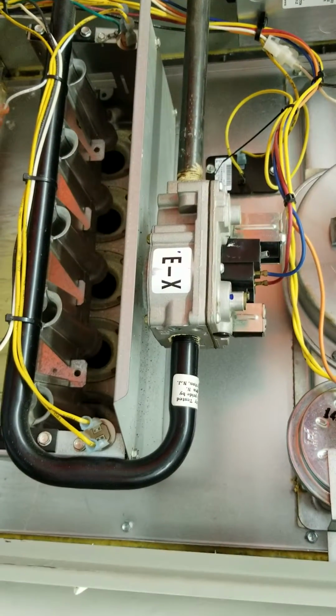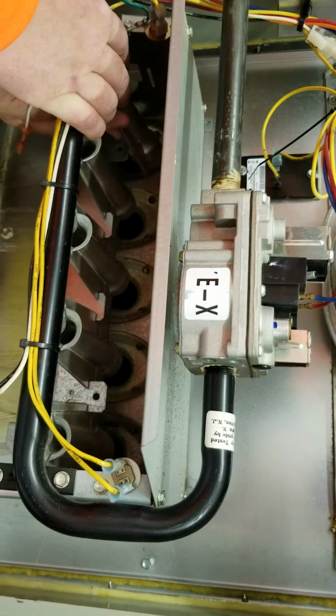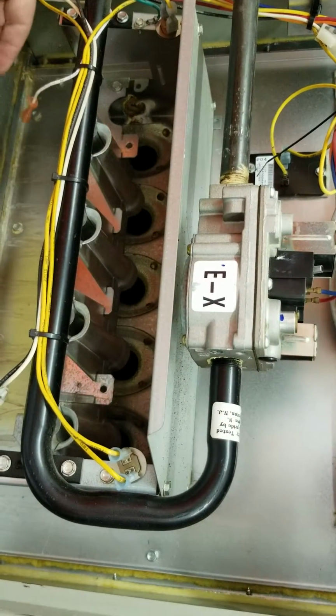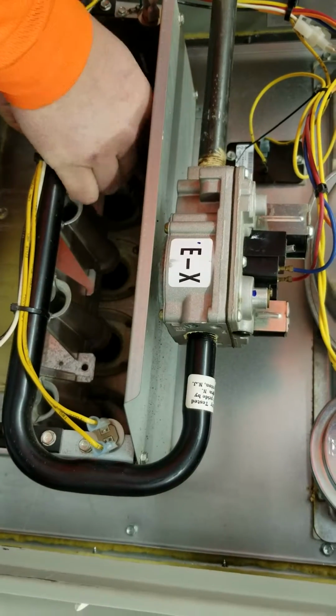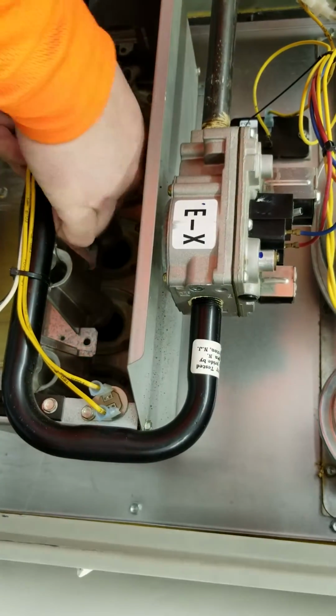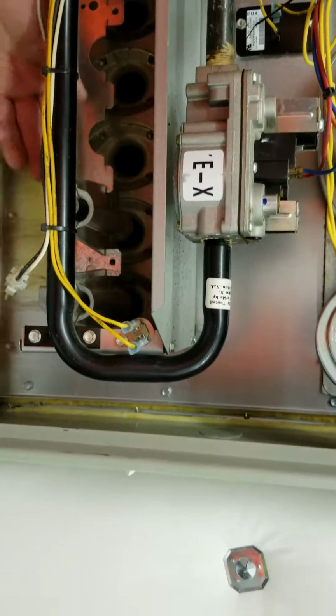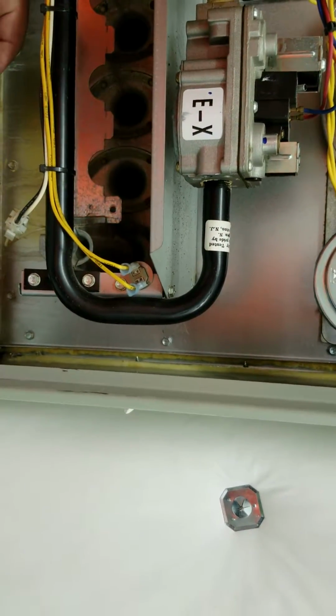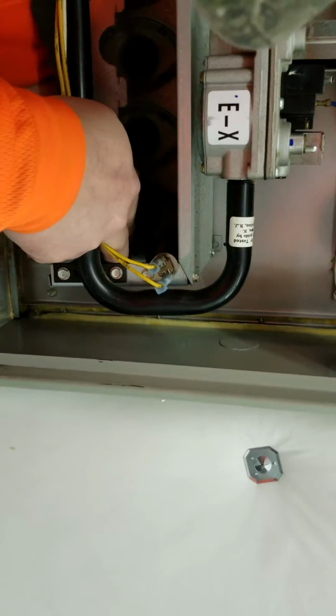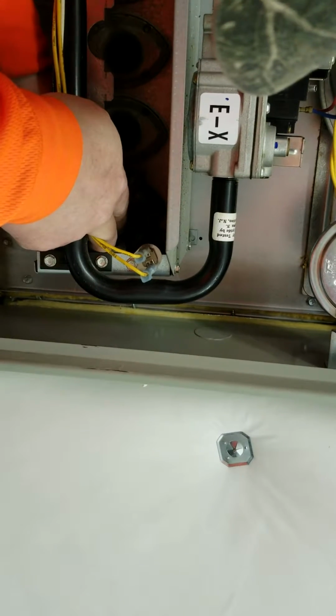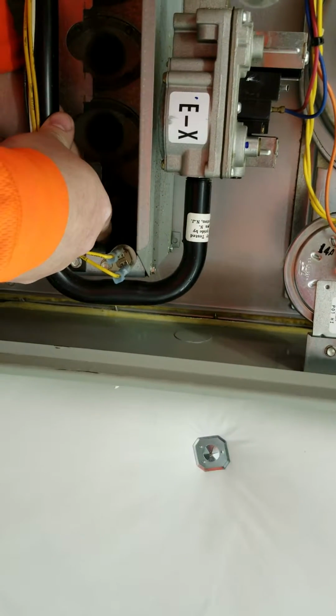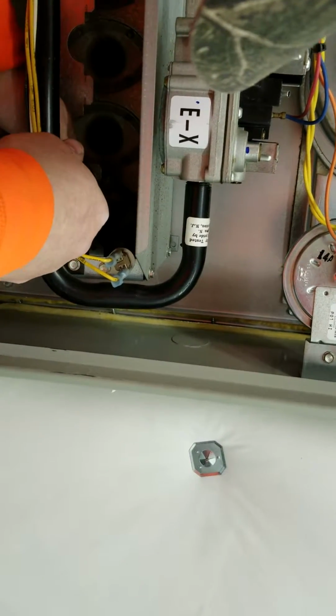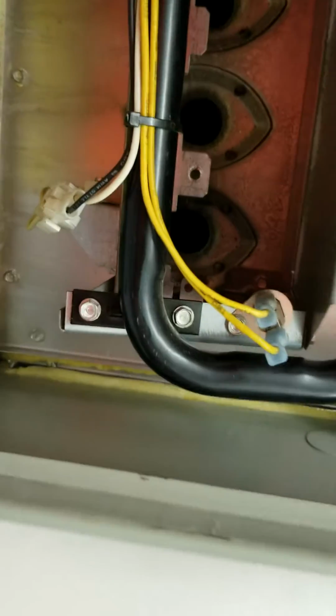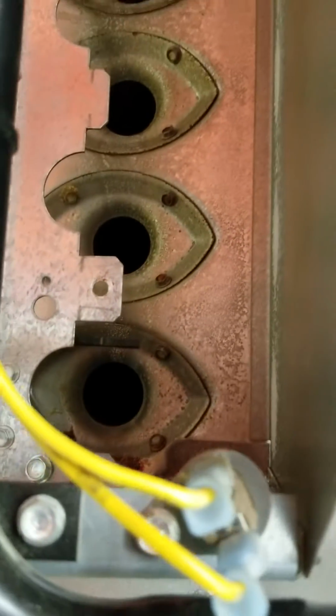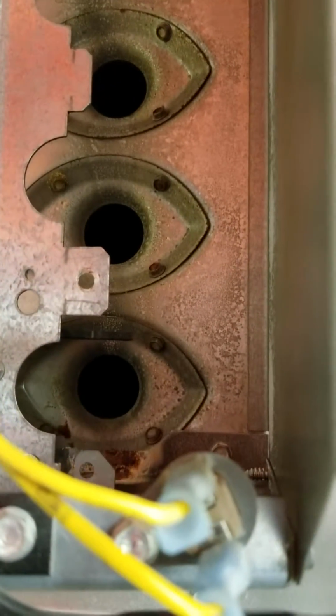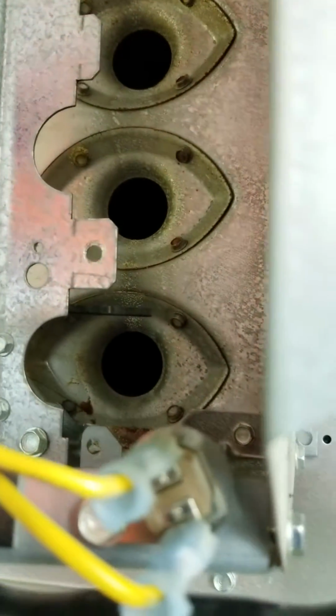Okay, go ahead, start from the left-hand side, lift it up in the tray, and slip them out. One. And keep track of how many burners you pull. 2, 3, in this case it's 5. This is the one where you want to be very careful so that you don't hit that igniter element. They'll take some abuse, but not a whole lot. And there you can see that igniter element a little bit better.